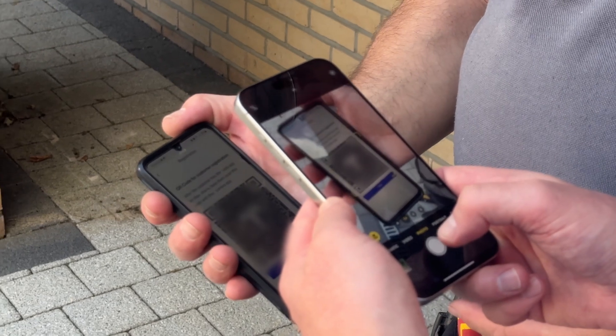At the end of Sam's install, our electrician Simon paired his phone with the Powerwall and showed him how to use and monitor it. To start with, they did a power cut test, where Sam put the Powerwall into off-grid mode. It changed over instantly and lights didn't even flicker.